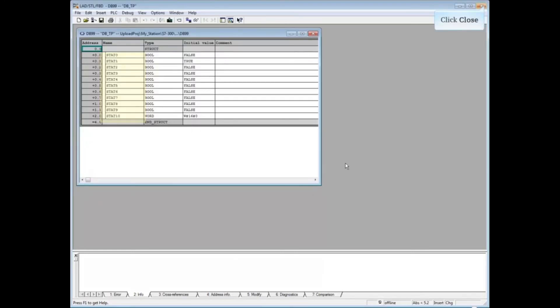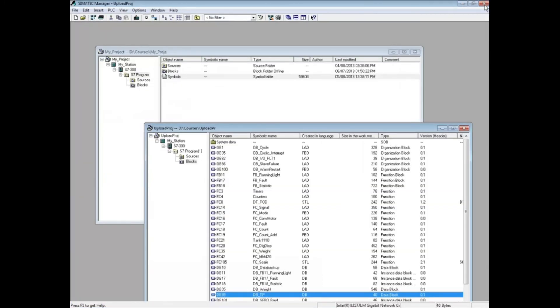The user defined names have been lost. While uploading a station is possible, be aware that you will not get parameter and local variable names in your blocks. Symbol names can be replaced by copying a new symbol table to the upload.